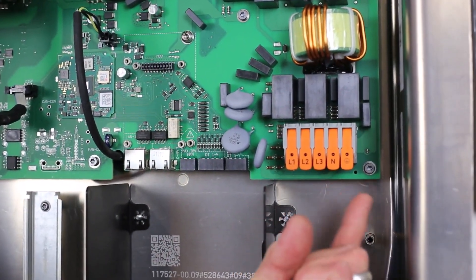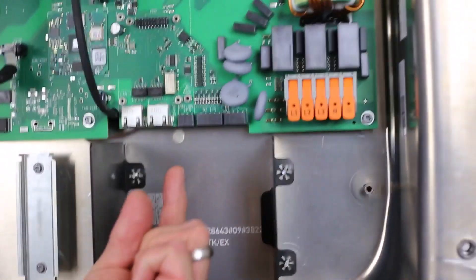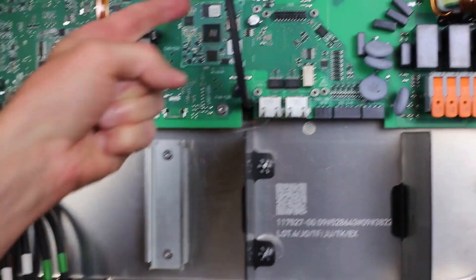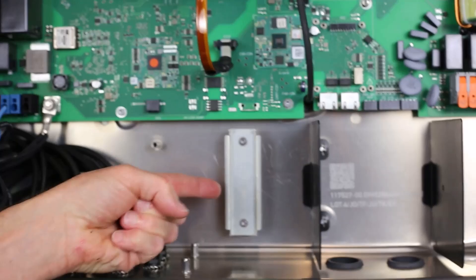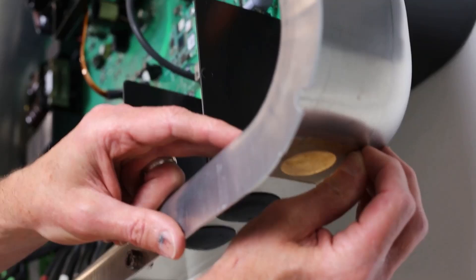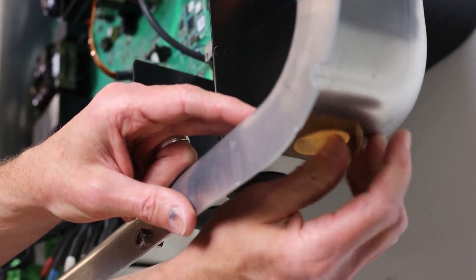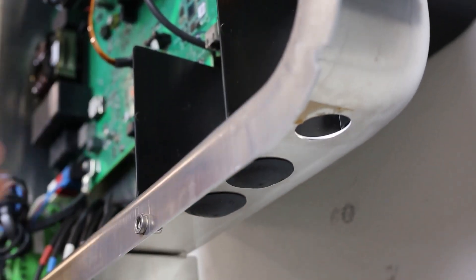Inside, you will find the AC terminals on the right side, the comms and IO plugs in the middle, along with the pin plug for attaching accessory cards. Here is where you attach the optional SPD kit. Start by removing the tape covering the 1 inch trade size knockout located below the AC terminals.